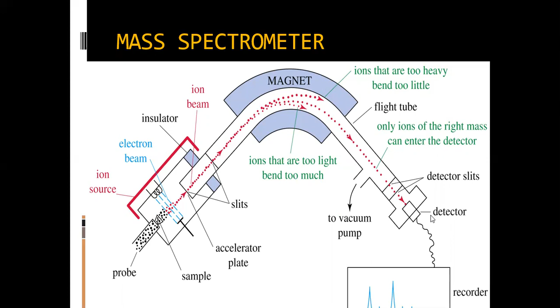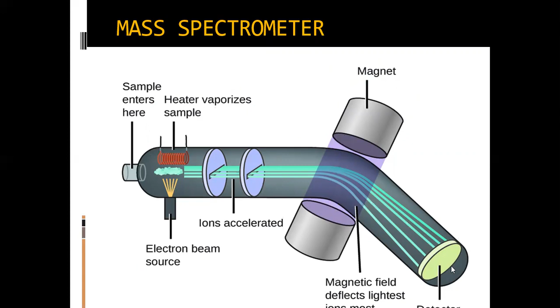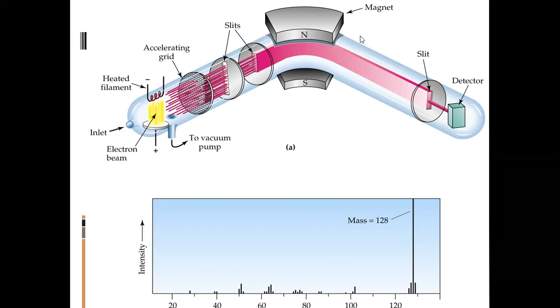Mass spectrometer. Sample enters here. This is where heat vaporizes it. This is the electron beam source. Here ions are accelerated, and this is the magnet. And here you can see the magnetic field deflects the lightest ions most, and here is the detector. Now this is the inlet from where the substance enters. This is the electron beam, heated filament, accelerating grid. This is the vacuum pump, and these are the slits, and this is the magnet, and this is the detector.